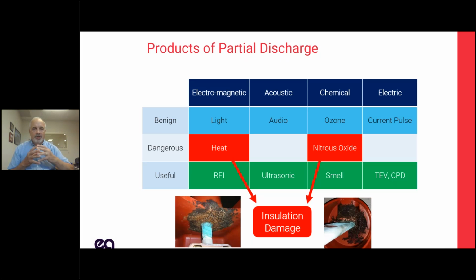When you have partial discharge, you have a variety of things that happen. Some of them we don't care about. We're going to call them benign. Some of those are very dangerous, and some are actually useful in finding PD. So going across the top, we've got the electromagnetic spectrum, which includes light, heat, radio frequency interference, anything that's in that spectrum. It generates light. Well, light is visible, and if I had a dark room and I stuck my head inside the switchgear, I could use that to find PD, but that's not all that useful.